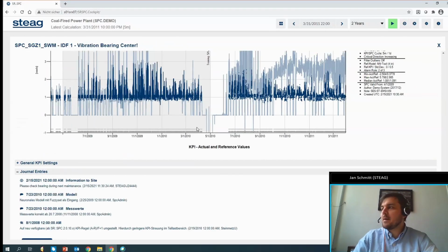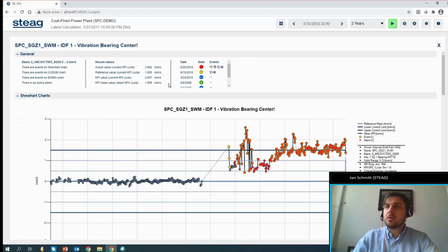If we open that up, right at the top we can see the history of the alarm, which is typically the first point you want to look at. Was there something similar in the past? We can see there are no critical things, except for the two warnings here. And then the latest point, at the end of June, is the alarm.